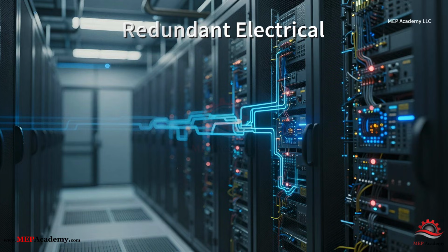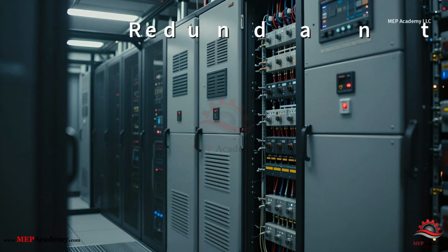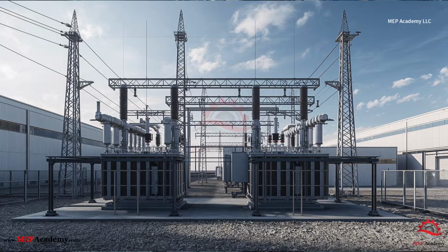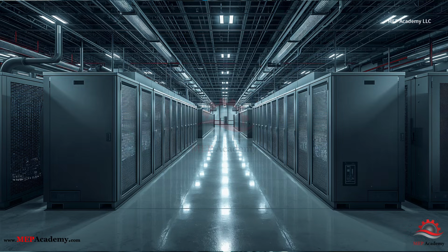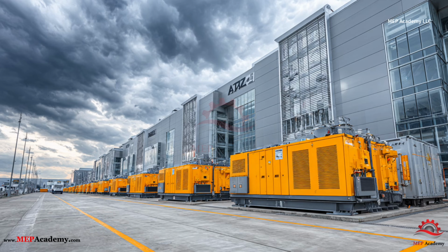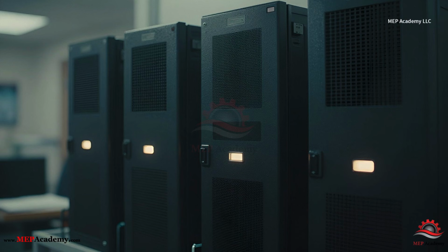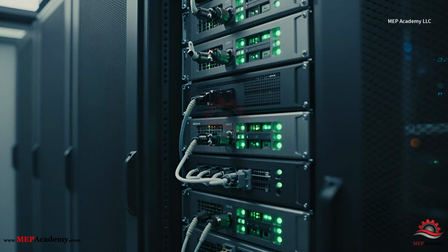Redundant electrical systems in practice. Electrical redundancy works the same way but with different equipment. A typical redundant electrical system may include dual utility feeds from the electrical grid, backup diesel generators, UPS battery systems, and redundant power distribution units. If utility power is lost, the UPS systems provide immediate backup power while the generators start and take over the load. If one UPS module fails, the redundant module continues supporting the servers. This design ensures continuous power delivery to the IT equipment.